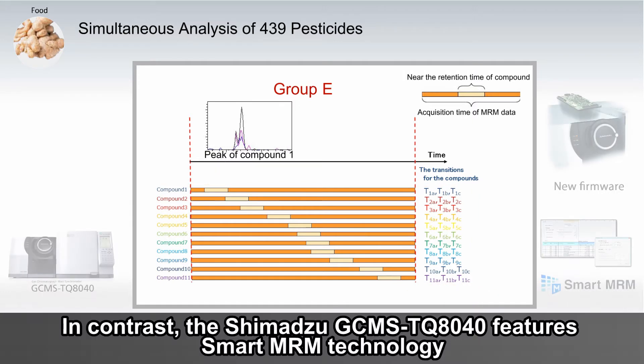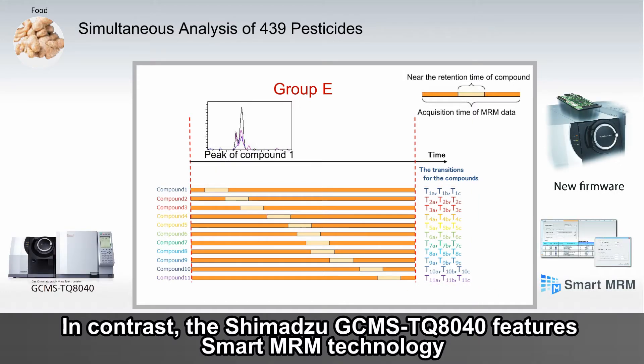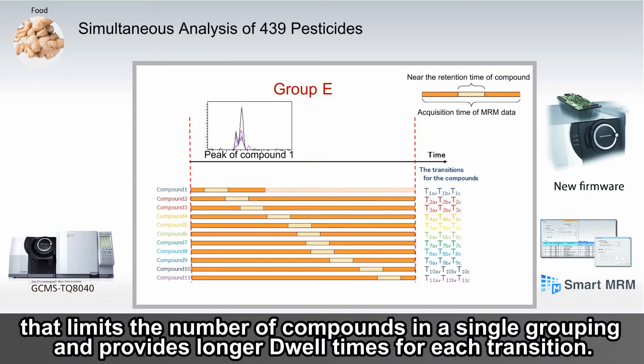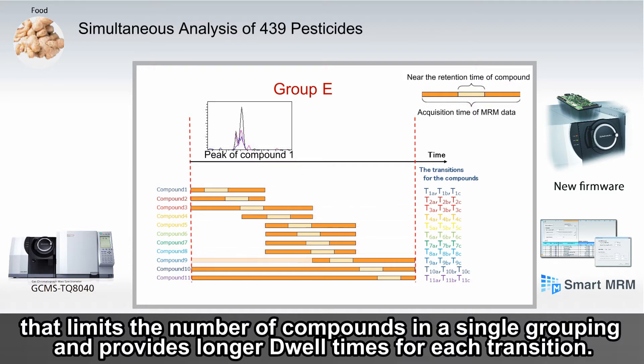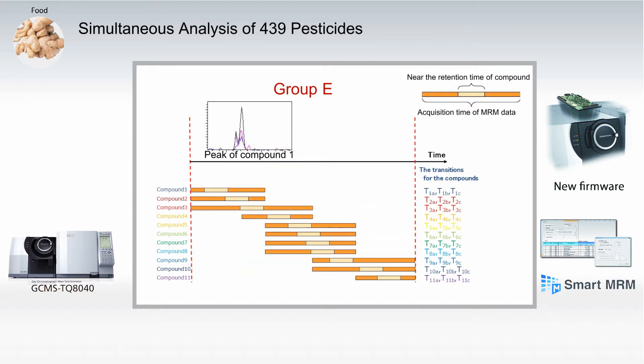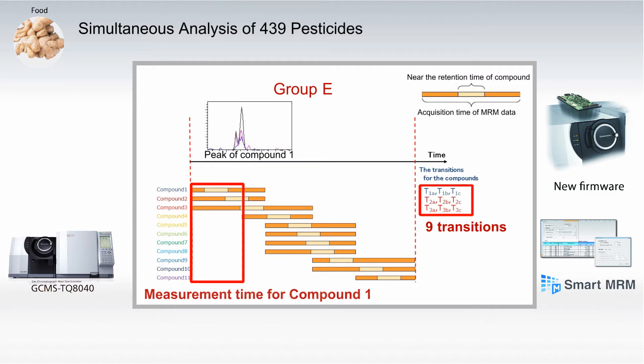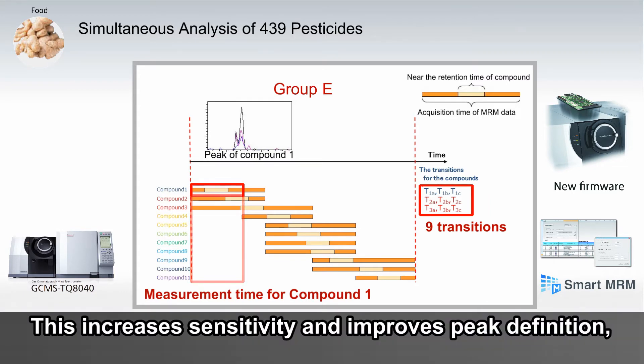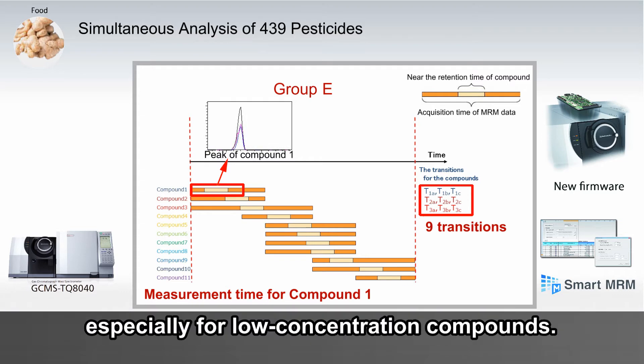In contrast, the Shimadzu GCMS-TQ8040 features SMART MRM technology that limits the number of compounds in a single grouping and provides longer dwell times for each transition. This increases sensitivity and improves peak definition, especially for low concentration compounds.